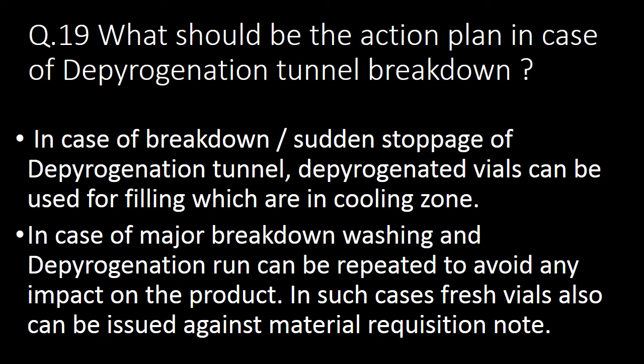Next very frequently asked question: what should be the action plan in case of depyrogenation tunnel breakdown? In case of breakdown or sudden stoppage of the depyrogenation tunnel, depyrogenated vials or ampoules in the cooling zone can be used for filling. In case of major breakdown, washing and depyrogenation run can be repeated to avoid any impact on product quality. In such cases, fresh vials can also be issued against the material requisition note.